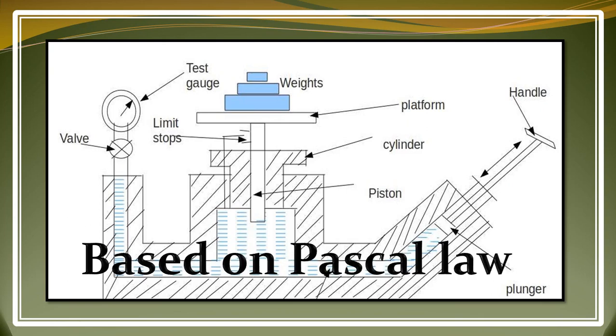So in the first situation, we close the valve and put some weight on it and pressurize with this handle until this piston goes free and reaches the limit stop value. On this value, we read the weight and calculate the output because this weight is proportional to the pressure applied. Okay, so we get the output pressure P, how much pressure is applied by this weight.